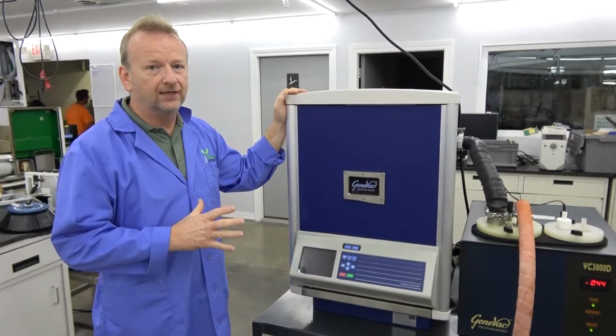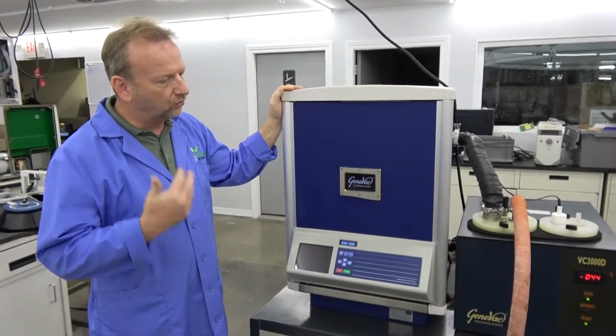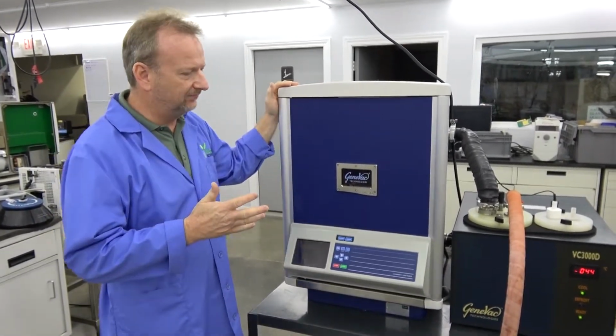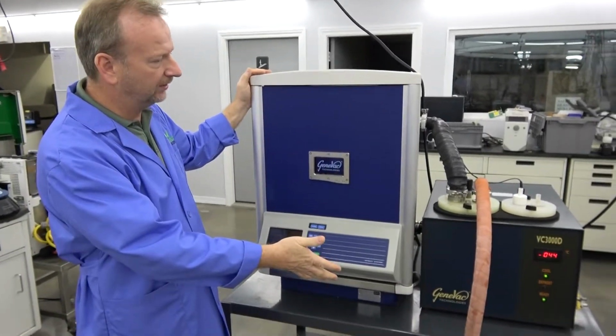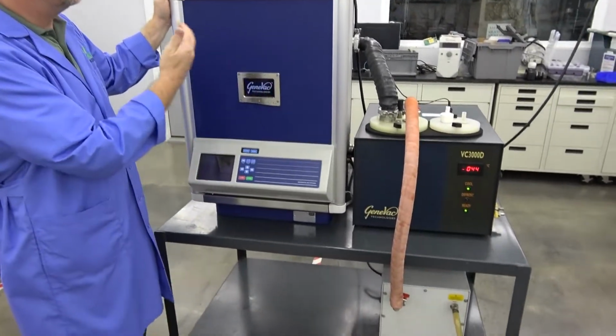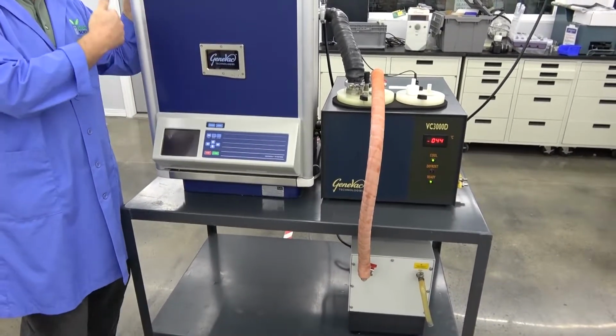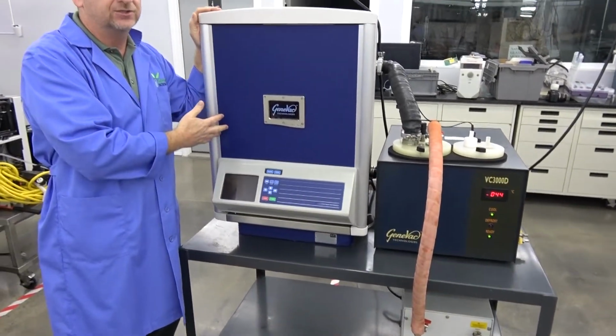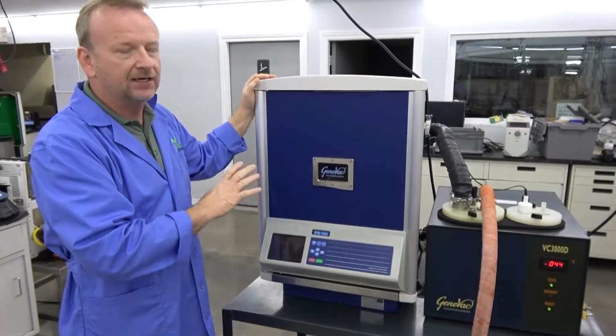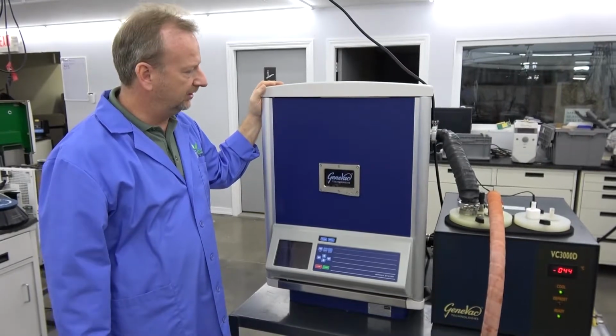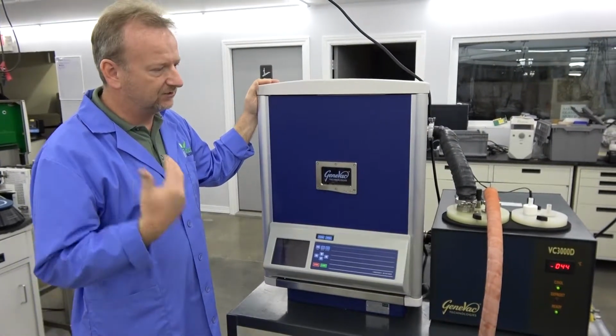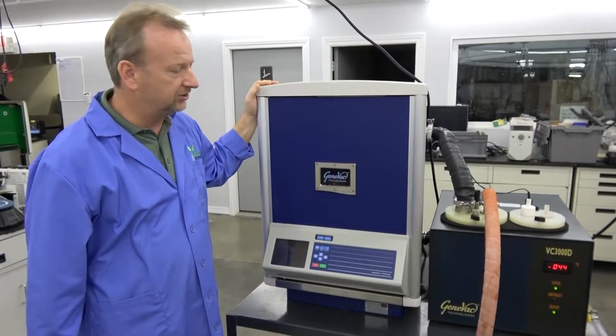And right now it is running, and I just want to point out how quiet the system is, because we've got the vacuum pump running, the condenser running, the centrifuge running, the cooling fans and the heaters and everything. And it's just a nice, quiet running machine. Works great. Everything seems to be working up to manufacturer specification.